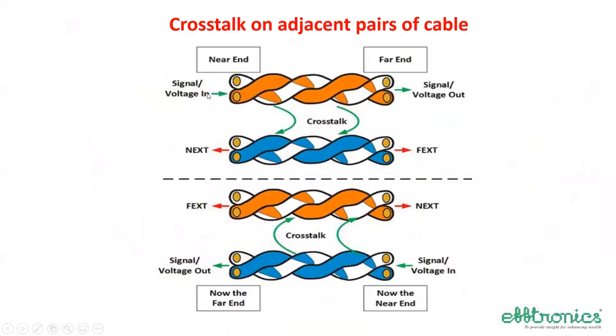Crosstalk is something like when we are using, let us say, the top pair to carry some signal, and then the second pair is also used for the data logger signal carrying. Whatever signal is traveling in the first pair can leak to the adjacent pair, and then it influences, it becomes a noise there. And when we measure the induced voltage at the near end, it is called near end crosstalk. And when we measure it at the far end, it is called far end crosstalk. These are supposed to be 55 dB less compared to the signal that is fed here. This has to be measured to see that the cable is fit for the axle counter.